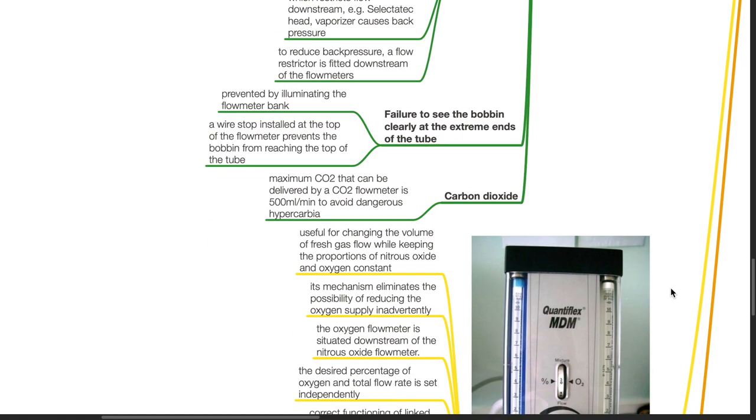Failure to see the bobbin clearly at extreme ends of the tube is prevented by illuminating the flow meter bank. A wire stop installed at the top of the flow meter prevents the bobbin from reaching the top of the tube.